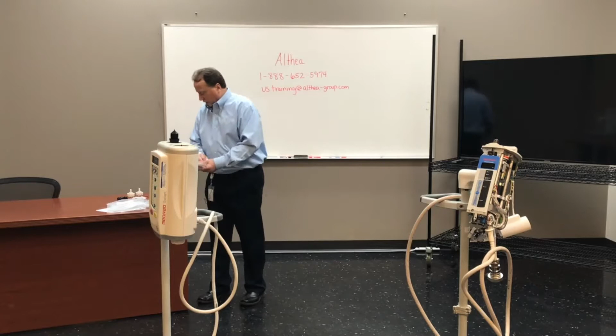We have the dual overlay assembly gasket, very common. It usually has to be replaced almost every PM—very seldom do I see one that doesn't need replacing.